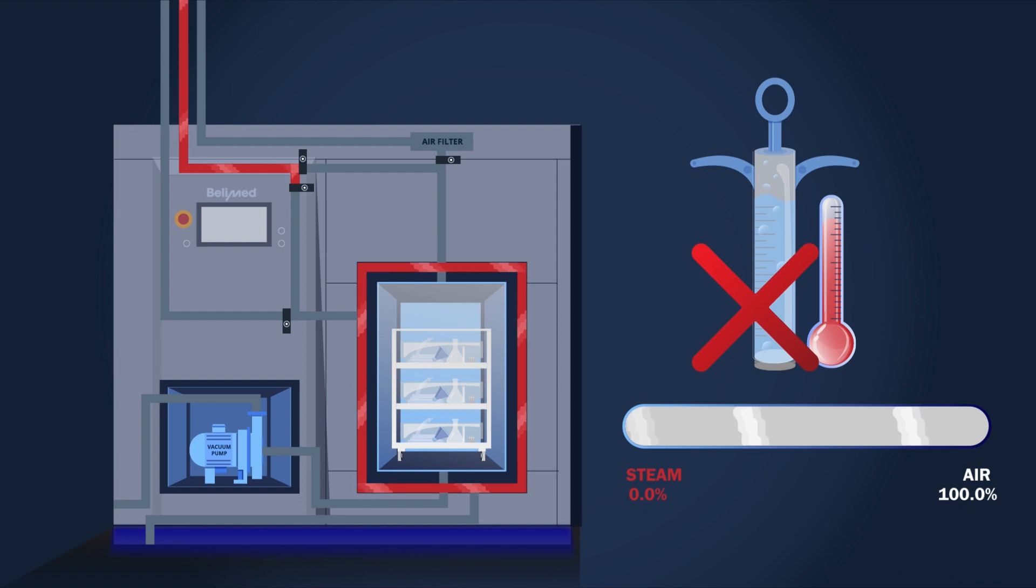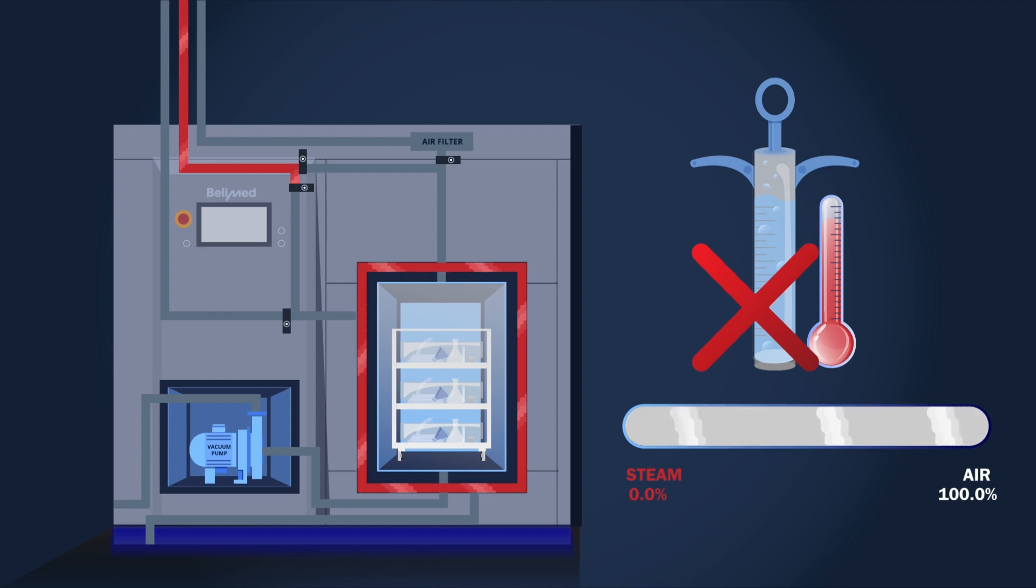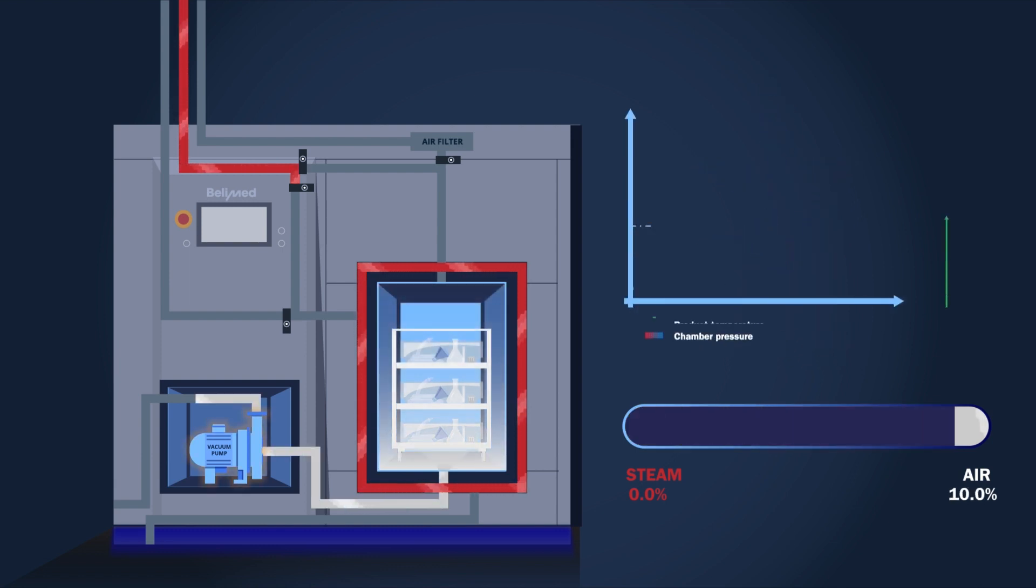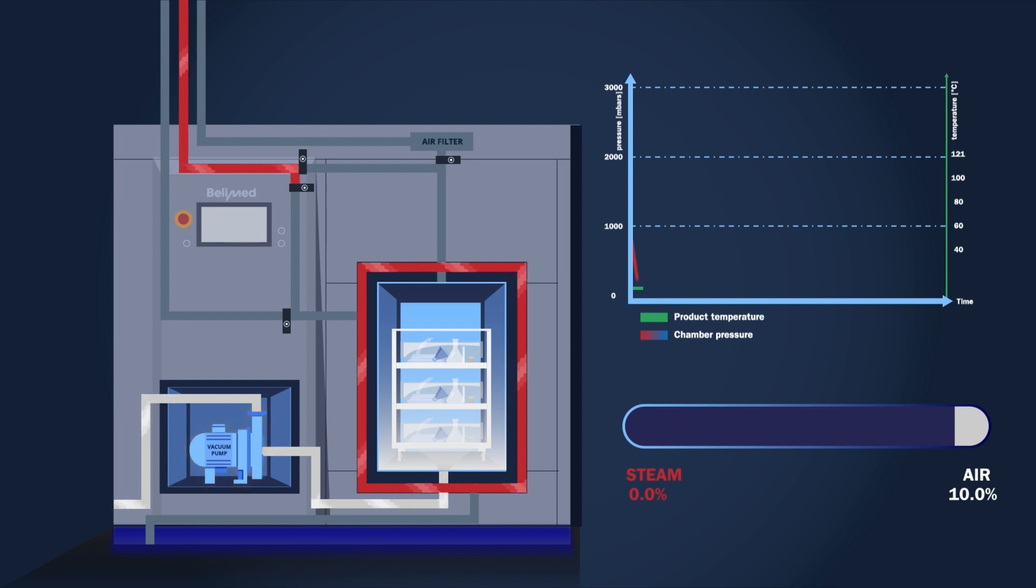When sterilizing open syringes, bags and ampoules, it is important to ensure that the liquids do not evaporate too much, which happens when the pressure is too low or the temperature too high. As air is a really good insulator, as much air as possible needs to be evacuated.